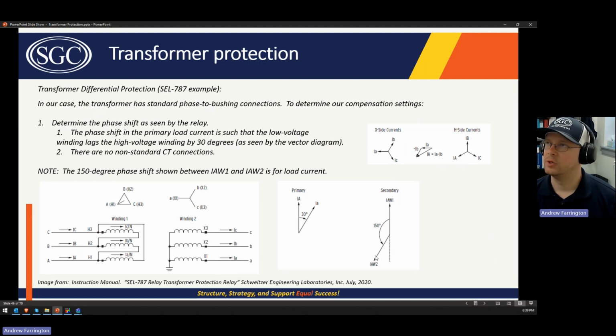And so in order to make those two currents 180 degrees out of phase for load current, such that when you add them together they equal 0, you would need to advance this in the counterclockwise rotation by 30 degrees so that they're 180 degrees out. Again, so that if you just added what the relay is seeing, it equals 0. So effectively, it's the same thing. The only time you really need to worry about this is when you have non-standard connections or a non-standard transformer. Most of the time, you could just say, delta is 0.